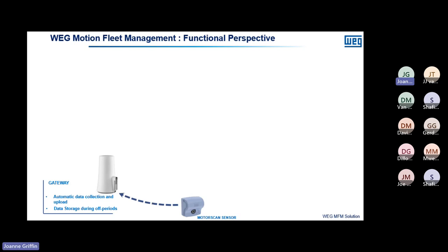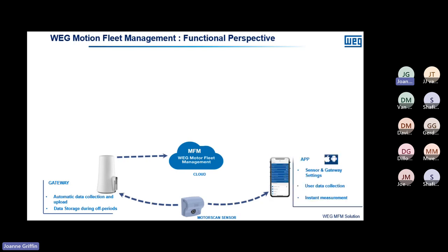The gateway sends the collected data to the cloud. Another way to send data to the cloud is to download an app from the app store. With the app downloaded, within about 10 meters of the sensor you can scan it, get data on your mobile device, and send that data to the cloud. However, there is a weakness with this approach — the availability of data on the MFM cloud depends on you physically going to the sensor and scanning it. The gateway approach is better because everything happens automatically without human intervention.